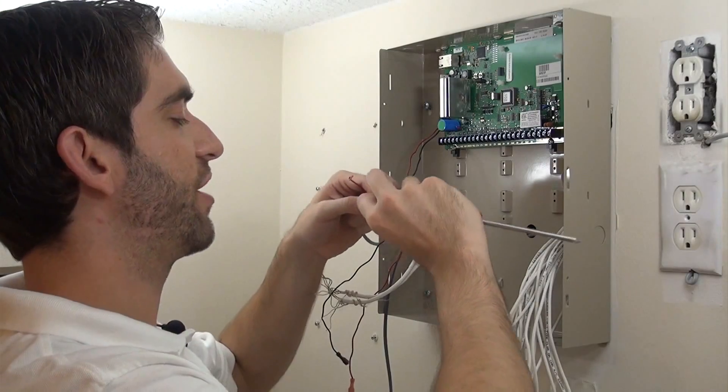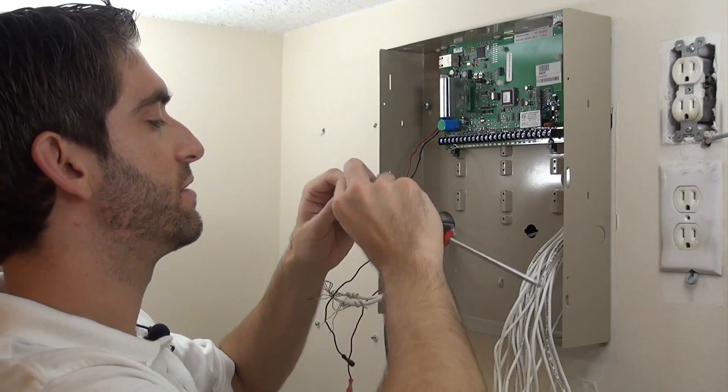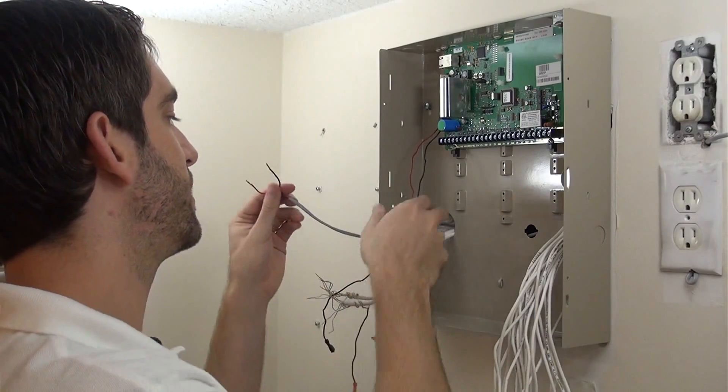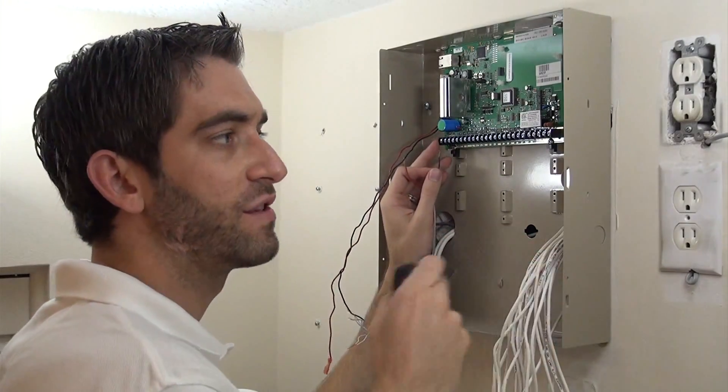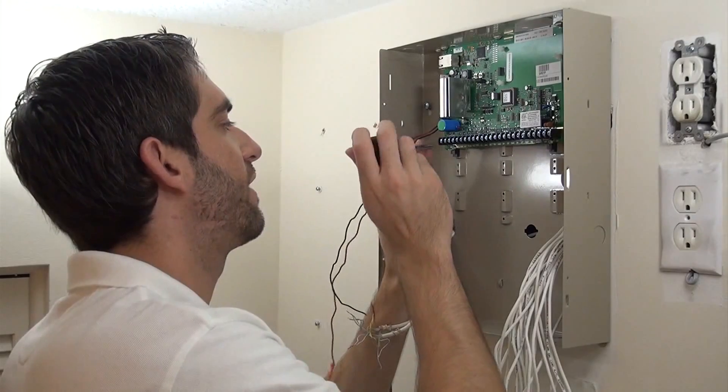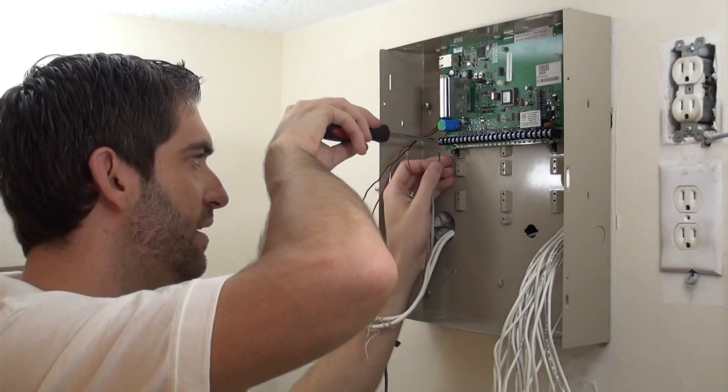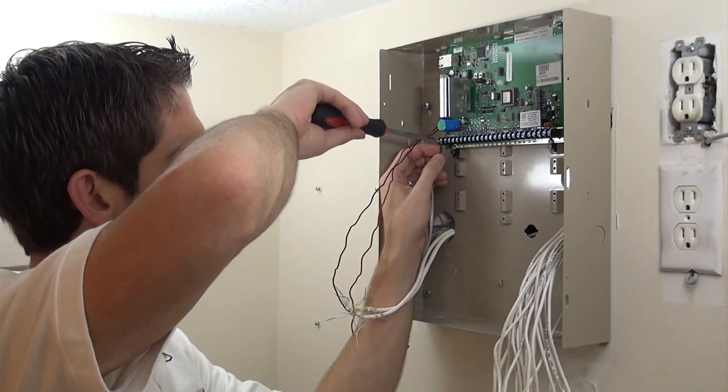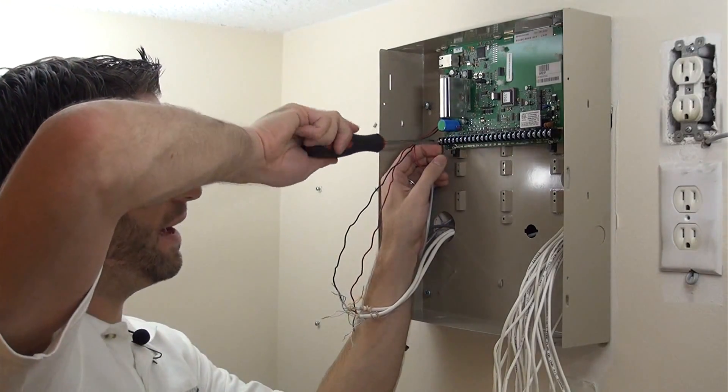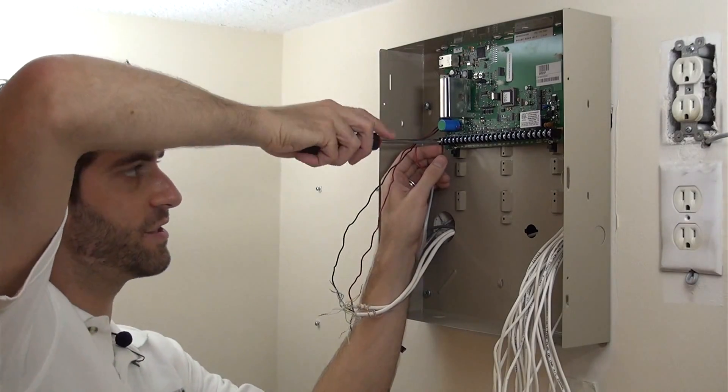Again we've got stranded wire here, so we just want to twist these down so it's a nice, clean connection into the screw terminals. Because the transformer is not plugged in, these wires are not live. So you unscrew the terminal, it gives you a little bit of room underneath the metal bracket and the back of the terminal, and then you just screw it down for a nice, tight connection.